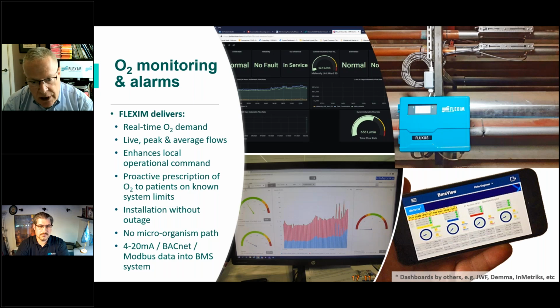FLEXIM's responsibility ends with our output, which might be 4 to 20 milliamp, might be BACnet, might be Modbus, into a BMS or an oxygen system. And then there are many other companies who produce dashboards. Top left is our sales partner in Scotland, JWF, and the dashboard they've effectively delivered to NHS Scotland. But there are other companies like Demma, Inmetrics, all doing great displays.